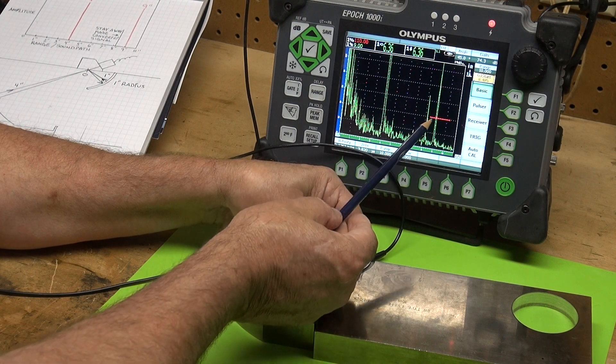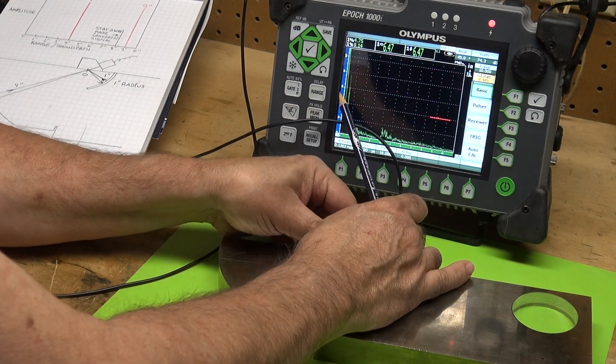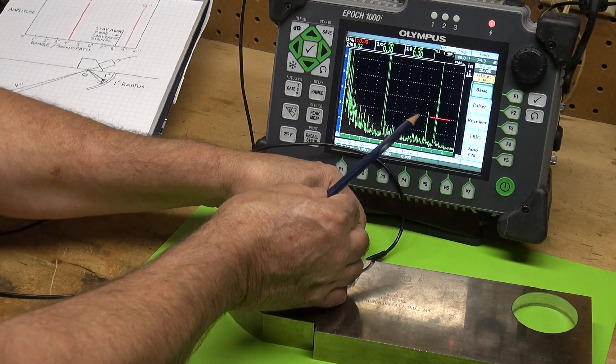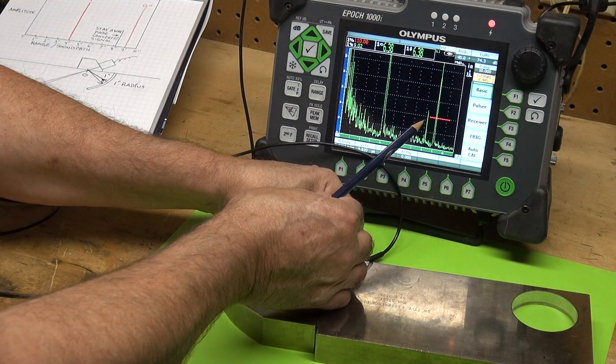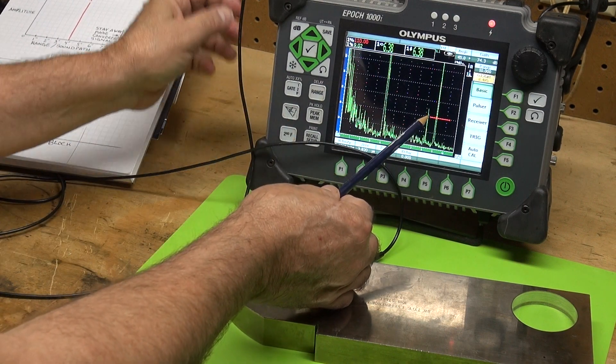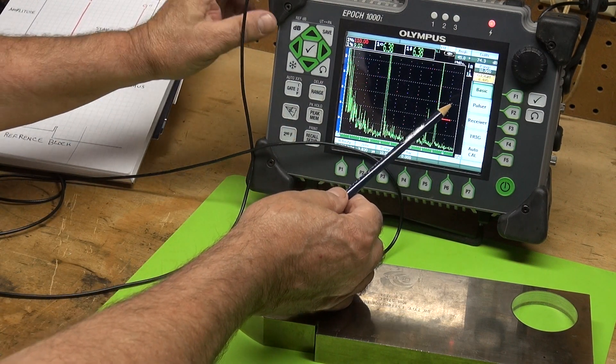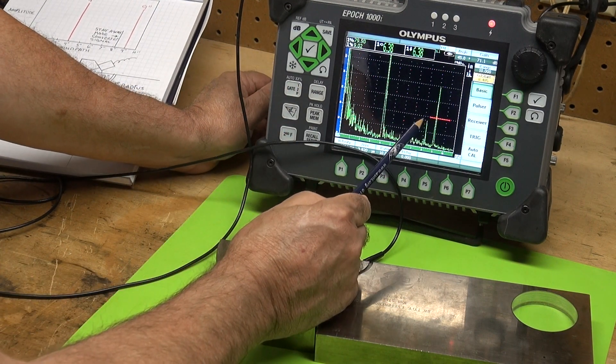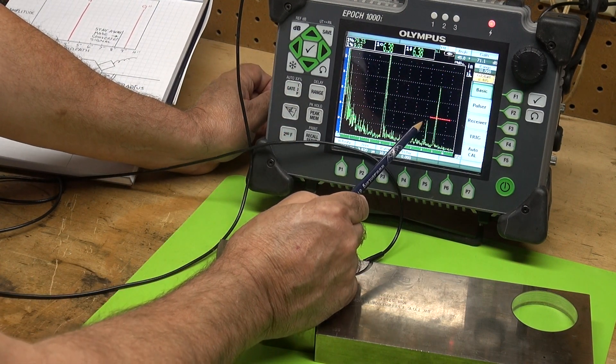Keep in mind if that signal is present, avoid it. Look, this is a good example. I have my gain cranked up a bit, but you see the mode converted signal? That's my good signal right there, that's my 9 inch reflector. You can see this guy's kind of enticing. Stay away from him.